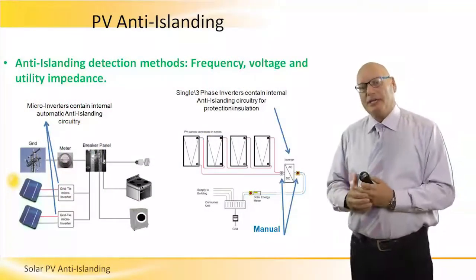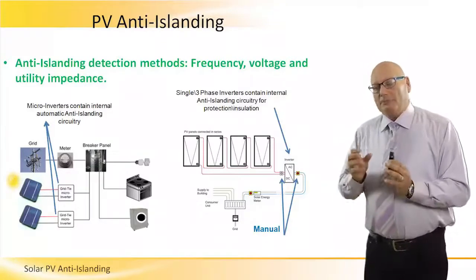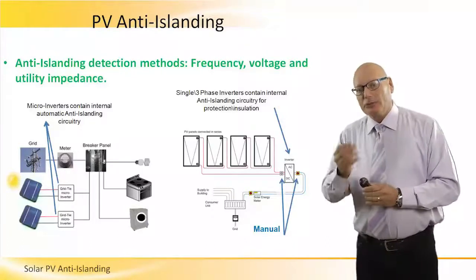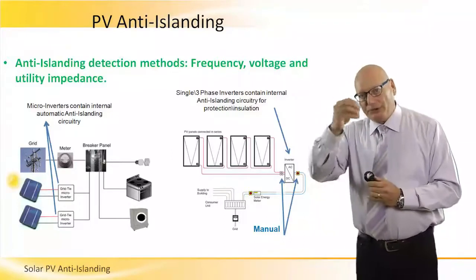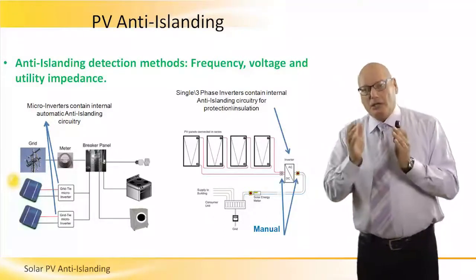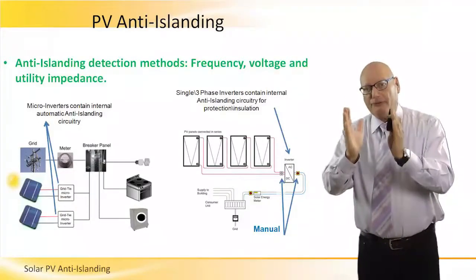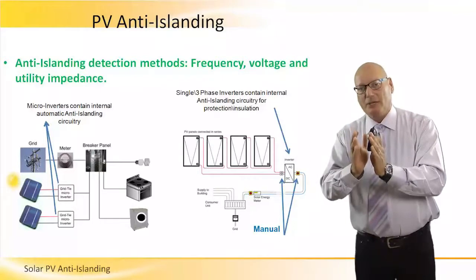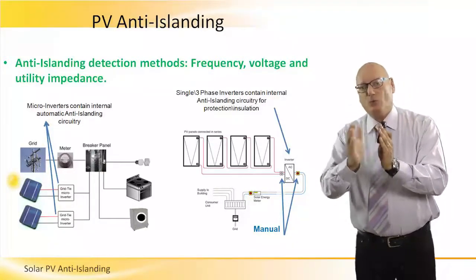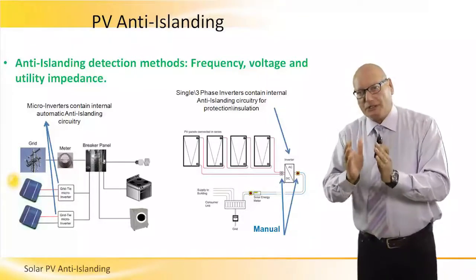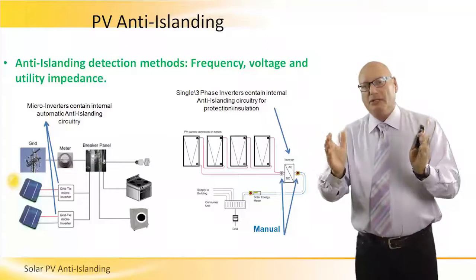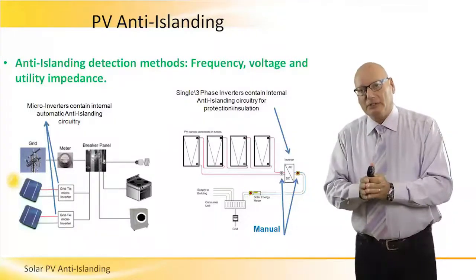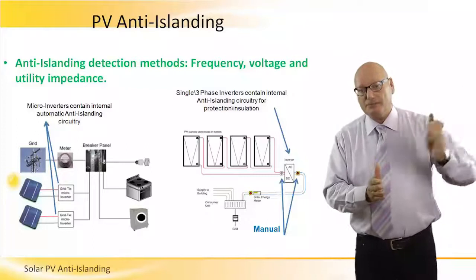The anti-islanding mechanism looks at three parameters: frequency, voltage, and utility impedance. This mechanism resides within the inverter and monitors the frequency of the grid — it must be within a very close tolerance. For example, in a 50 Hz system, the tolerance would be plus or minus one hertz. If the frequency of the grid goes beyond these tolerance levels, the anti-islanding circuitry will automatically cut and split the grid from the PV system.